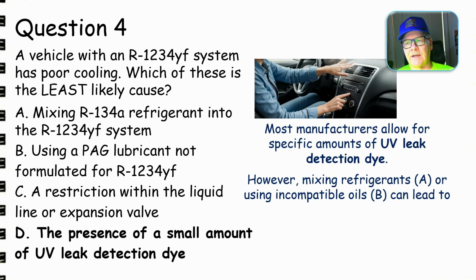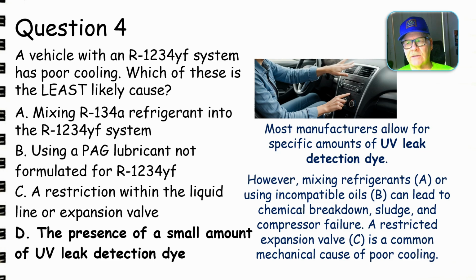Typically, you can put a little bit of dye in there - it's not going to hurt anything. But mixing refrigerants or using incompatible oil, and so on, will cause problems. You can see all these other answers and why they're right, and this one is wrong for this question - it's the least likely cause just because you put some detection dye in there. That's the reason it says 'small amount'. If you put a lot of dye in there and it's mixed with the wrong kind of oil, it can eat the insulation off the wires in the electric compressor and cause it to melt down, burn up, whatever.